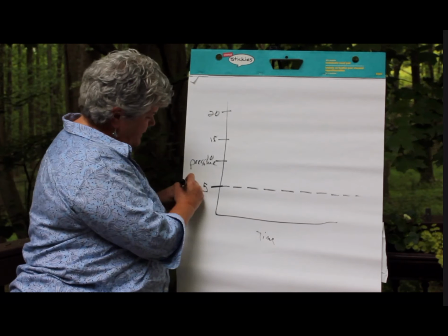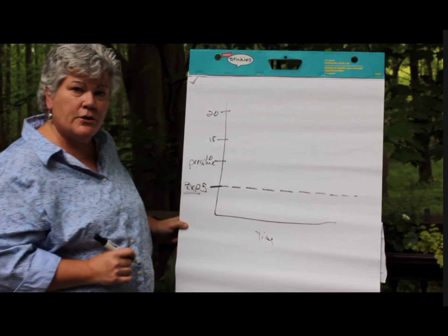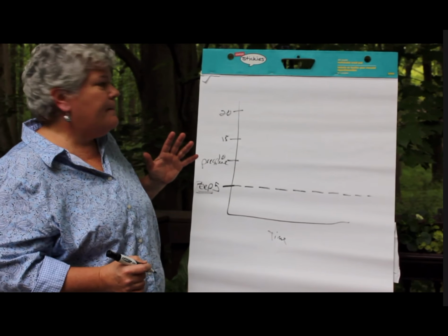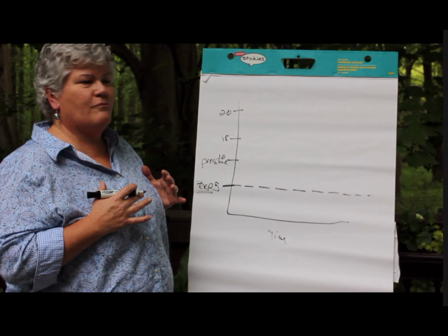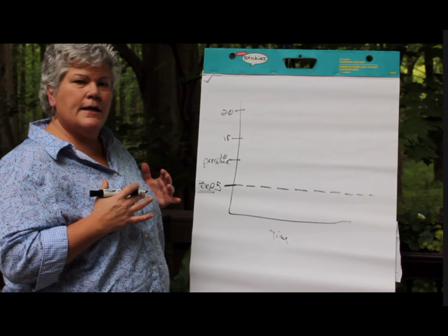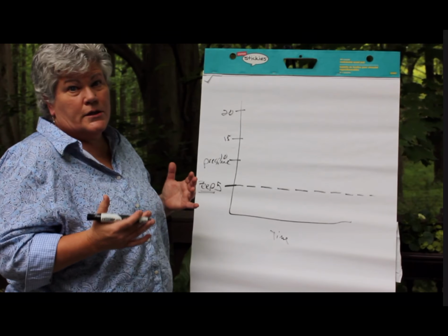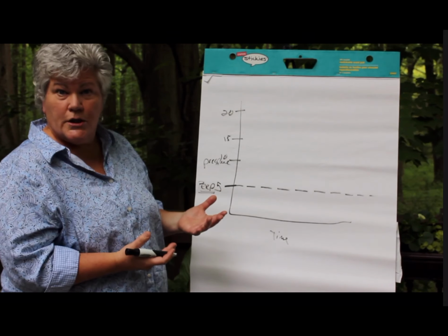So that PEEP is there all the time, positive end expiratory pressure. Then we have to tell the ventilator to give some type of peak inspiratory pressure. This is what's going to make the baby have breaths. The chest is going to move, and that's how we can tell whether our ventilator is doing its job, if the chest is moving. Just like when you look at someone, you can tell they're breathing because their chest is moving.